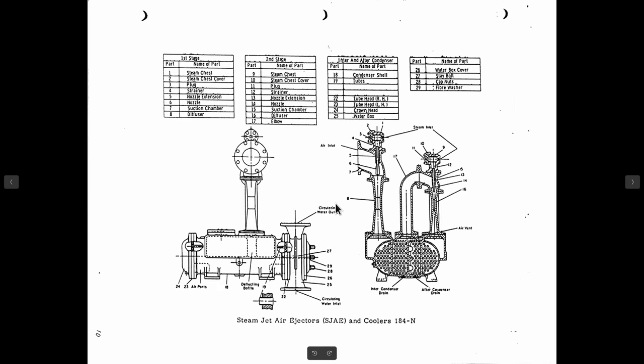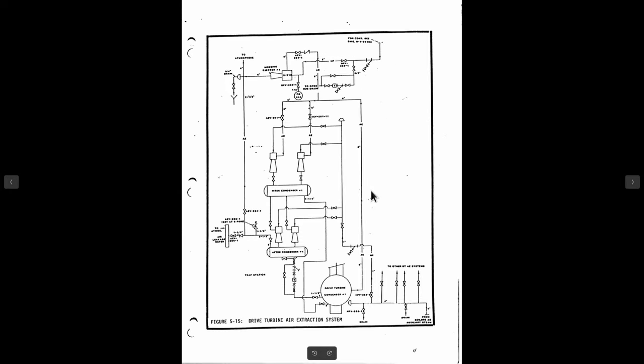Now, this is the steam jet air ejector. We threw these in here - it's on the 184 end, but 109 was the same design. Basically you have a steam nozzle that creates a low pressure in here. As you create a high velocity, you create low pressure, so it pulls the air in. Down here you create a slower velocity and raise the pressure. So these will pull a pretty good vacuum - that's why you have two in series, it can pull it down very low. That's just an overview of the drive turbine air system.